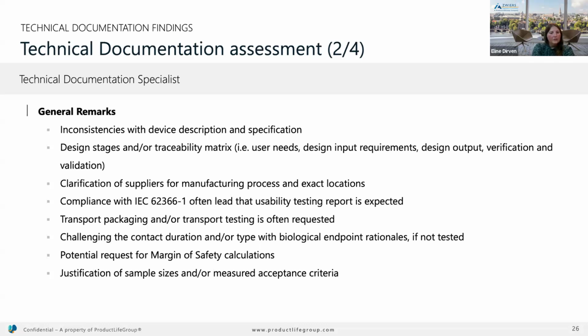Then related, we see quite some focus on the transport packaging and/or the transport validation testing, whether that's performed. So does your device remain stable also after transport? Then for specifically the biological evaluation, they may challenge your contact duration or what it is in contact with. And also if you haven't performed all the tests, which is definitely not always needed, they may challenge your endpoint rationales.